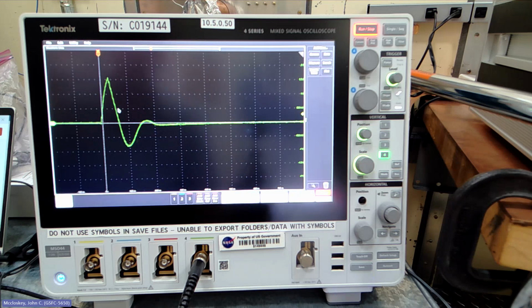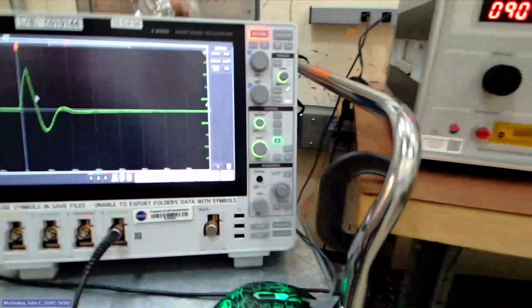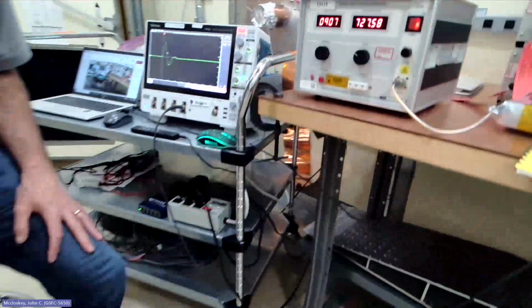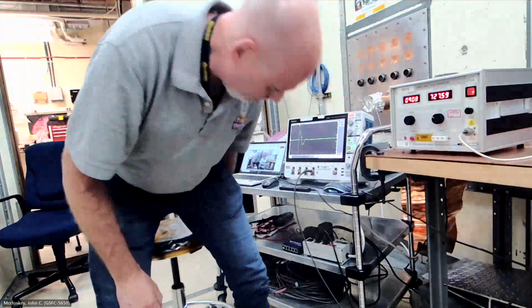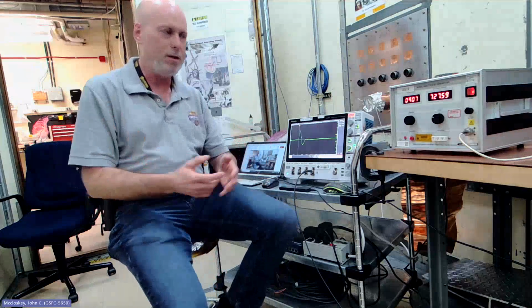It's giving you those fast rise and fall times to stimulate the cable and give you that response, and then just see how much of that energy is coupling onto internal signal lines that causes some perturbation that you might observe in your equipment under test. And that's really the whole point of the test: how susceptible is your equipment to these kinds of transients that might be impinging on these cables that are connected to your box. So that is basically what I wanted to show you.